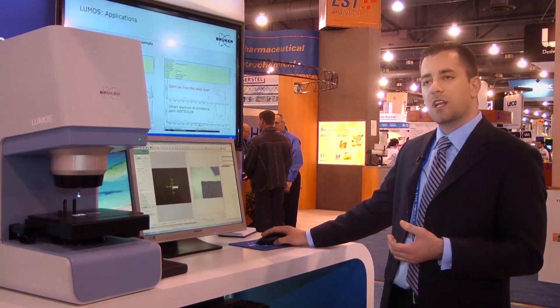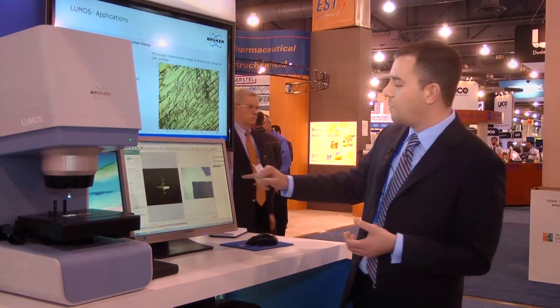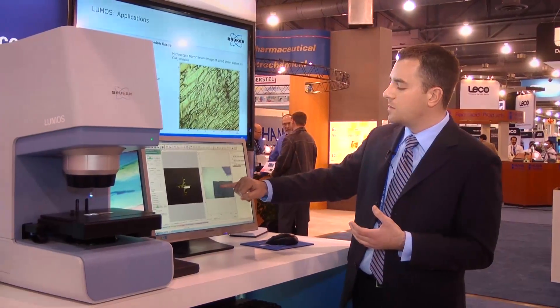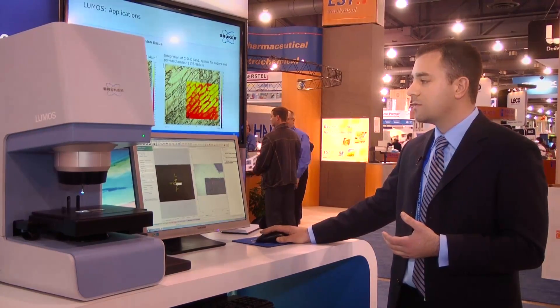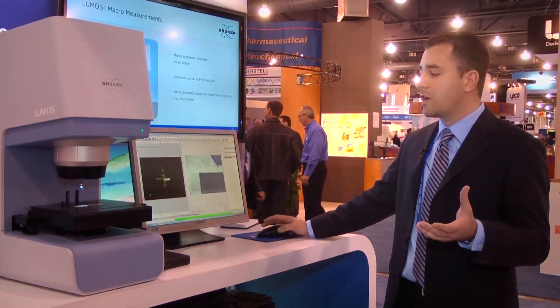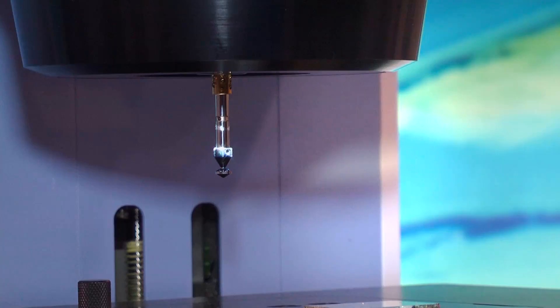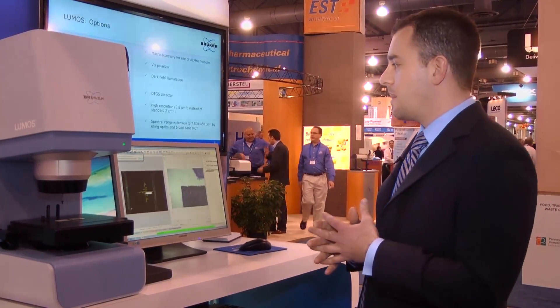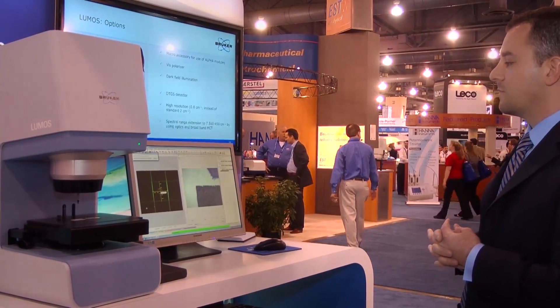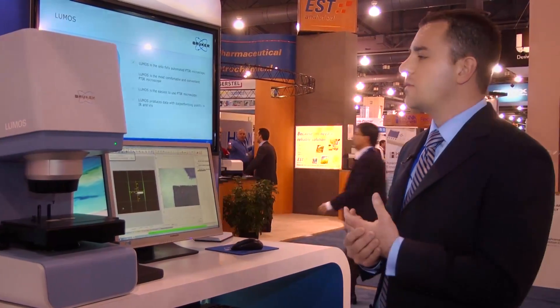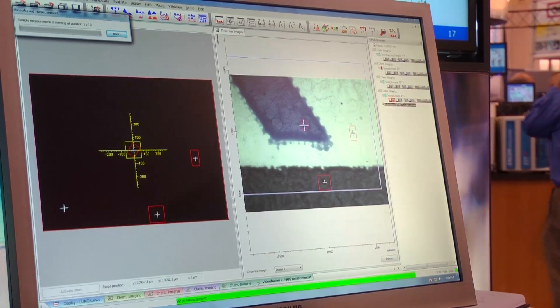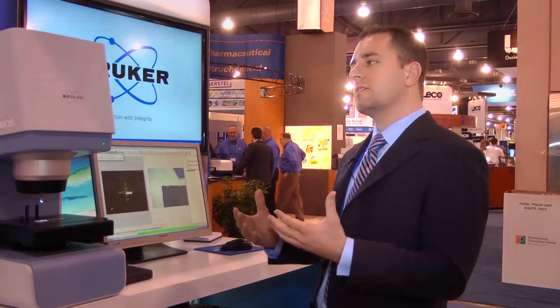I can also switch between the different pictures I collected previously, and all of these pictures are saved with my spectra. I want to see if there's a difference between my blue ink, my black ink, or no ink. I'll take individual spots here, name my sample, set the number of scans, and click measure. All of the automation doesn't close down the fact that it's a really high-performance system. We've marketed this to routine customers for the ease of use, but also to research-based customers for the high-performance spectra you're able to achieve. You really get the best of both worlds.